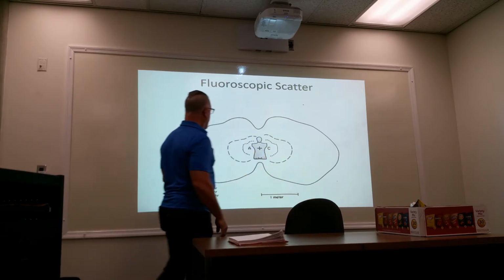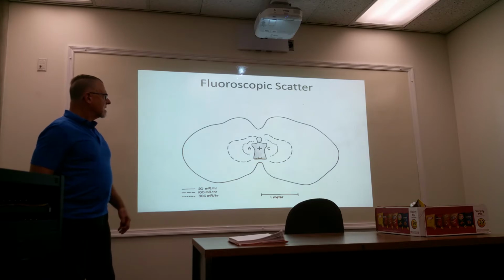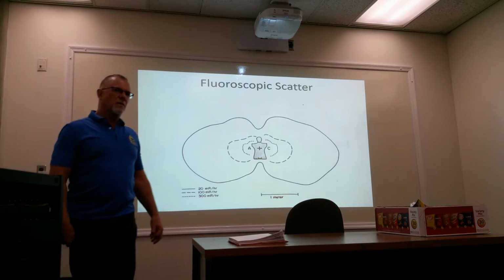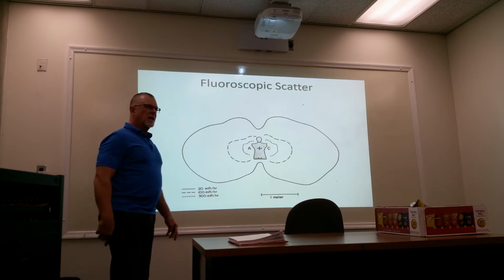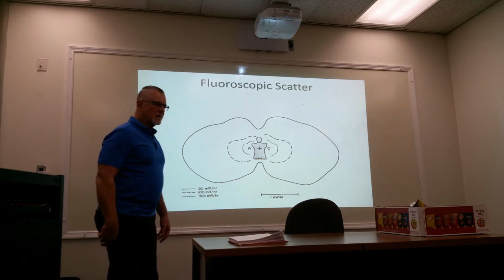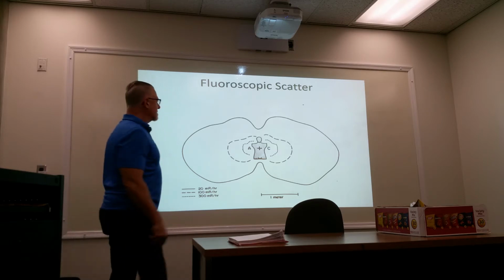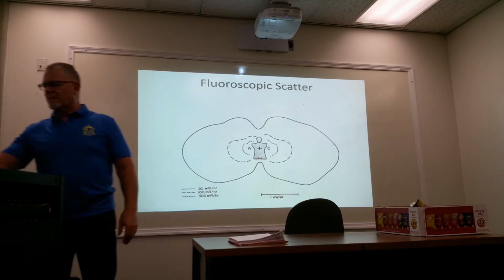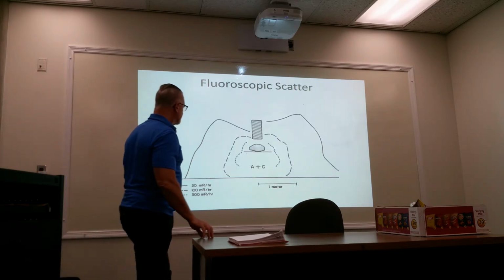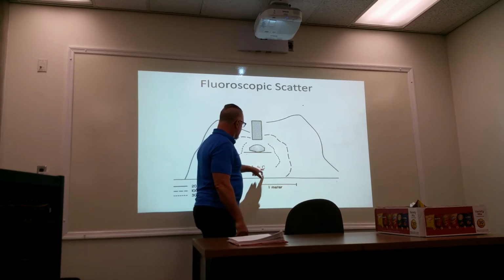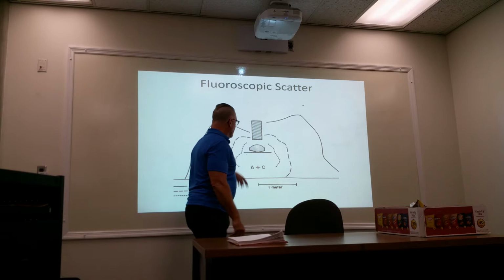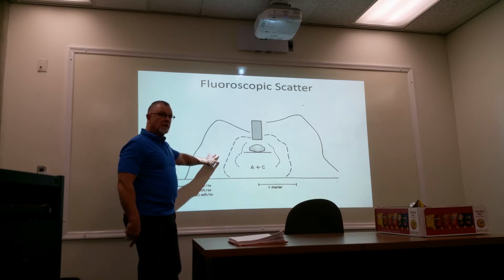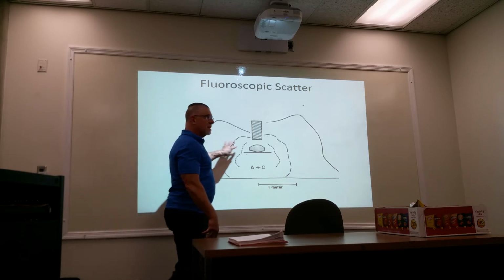Okay. The cathode side and the anode side, you'll see on the next slide, is slightly different. Anybody think of why that might be? The intensity's hotter on the cathode side. No? Hint? Anode heel effect. Heel effect, yeah. So from the head end, you've got the anode, cathode, so the heel effect does play a part. So again, this lets you know that if you can stand on the anode side of the tube, you're going to get slightly lower exposure than you are on the cathode side.